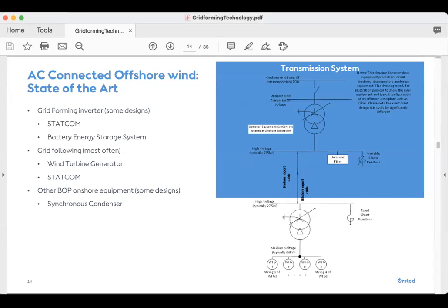And the reason we do it is because our wind turbines, if you look at the single line diagram, are located in the ocean. And typically there would be a turbine transformer that transforms it to 66 kV. And then on the offshore substation side, you have another high voltage transformer that typically transforms it to 275 kV. And then you have this long export cable. So if you take into account all the impedances, the transformer impedances and the cable impedances, there's really no way we can utilize the turbine reactive power control capability. So we need additional devices onshore, most often to meet the grid requirements, and also sometimes just to make sure we can ride through some events.